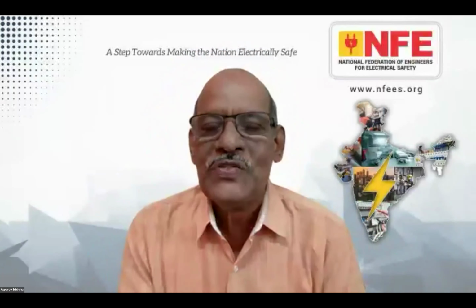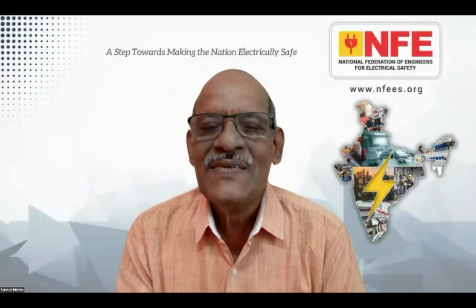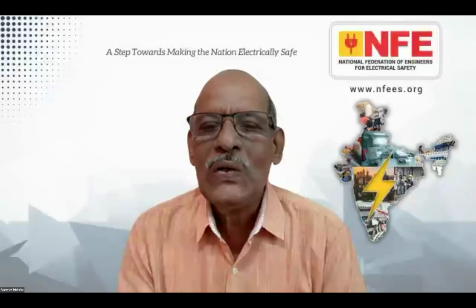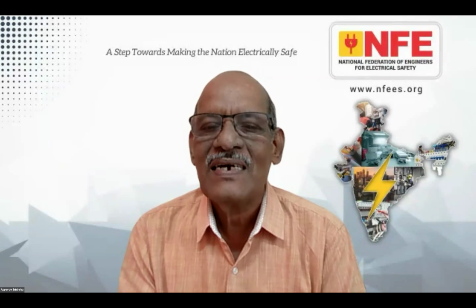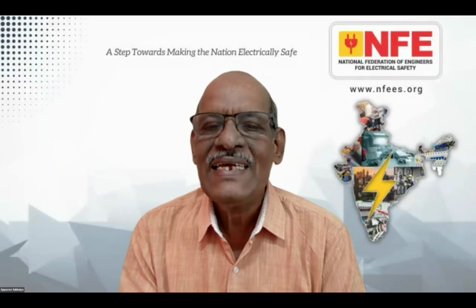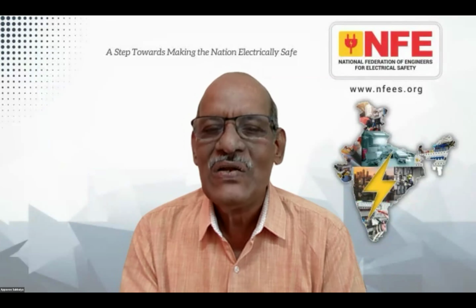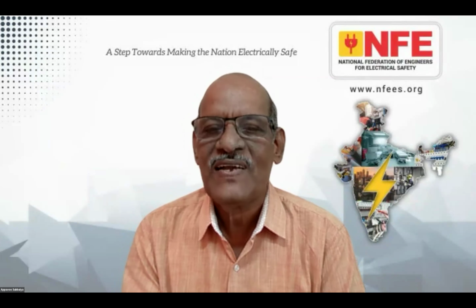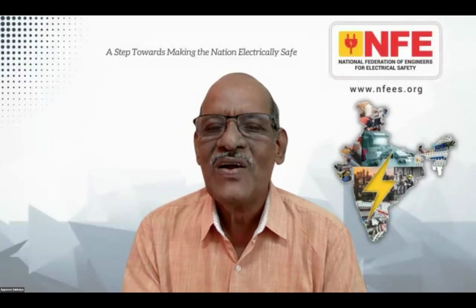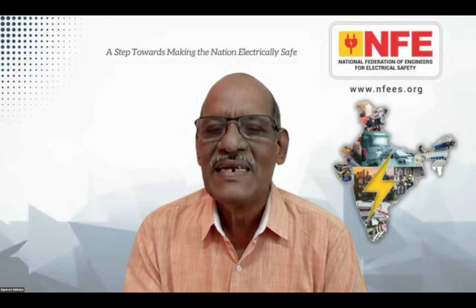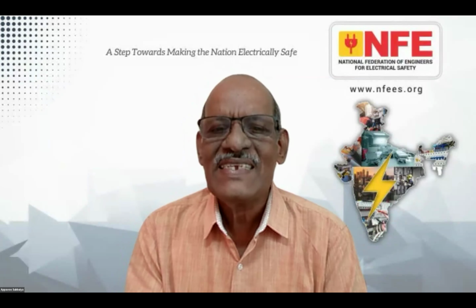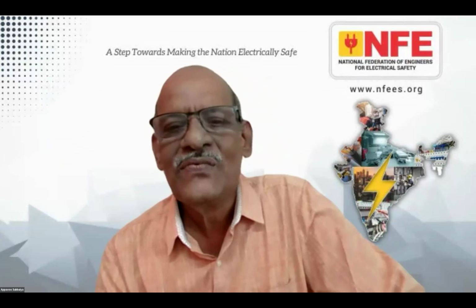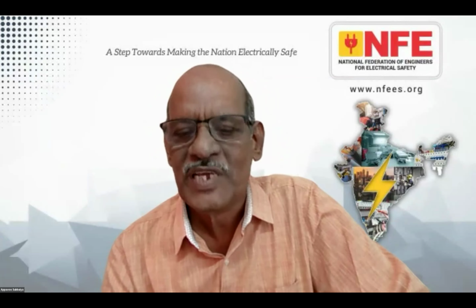As a doctorate, you should know that in ST, the protective conductor alone is not the fault return path. In LT, the voltage is very low, 240 volts or so for an earth fault, so that can be safely brought back through the PE conductor alone. On the HT side, it's a grid. So earth fault loop impedance is not applicable there.